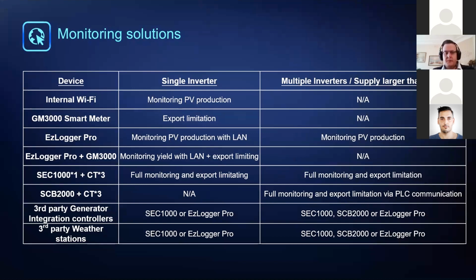With the EZ-Logger Pro, it gives you the optional LAN. So it can give you the above functions as well as LAN. If your inverter is outside in a plant room and you need to run LAN cables for that, it's best to use an EZ-Logger Pro. The GM3000 can also work with the EZ-Logger Pro to give you that export limitation.